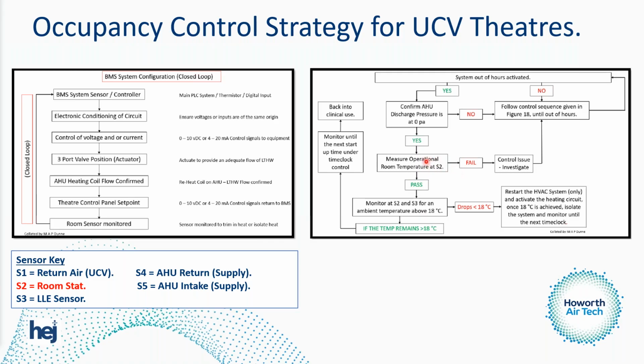Don't forget, this is an educational document. In reality we'd probably use S3, the low-level extract sensor - I've highlighted that because room stat sensors are advised against in HTM. We monitor at S2 or S3 for an ambient temperature of 18 degrees, remembering the HVAC system is off now. If the temperature drops below 18 degrees, we trickle the HVAC system back on, open the heating circuit, get a bit more heat into the room, achieve 18 degrees, then switch back off. We can do that in the morning until about 8 AM, then bring the HVAC system back to full speed, get 22 air changes back in there, and away we go.